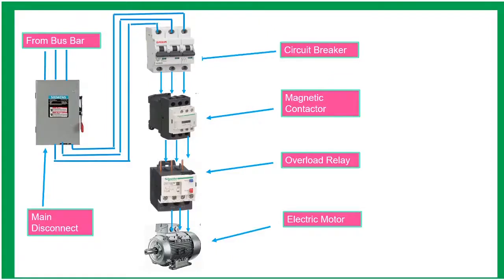This is the usual setup of motor control, from the bus bar going to the main disconnect. The purpose of main disconnect is to shut off the entire circuit. The circuit breaker is designed to protect electrical circuit from short circuit and ground circuit interruptions. Contactor is an electrically controlled switch used for switching higher current. Overload relay is designed to protect the motor from prolonged overcurrent which causes overheat and destroys the motor.